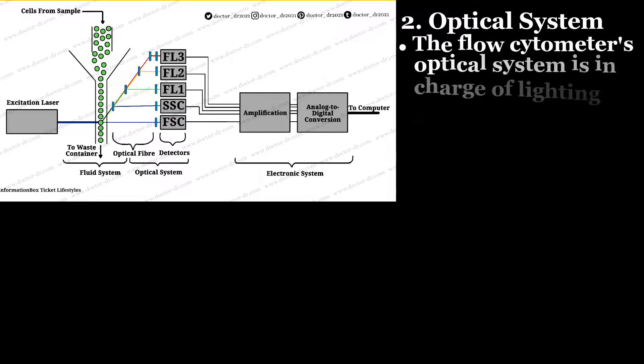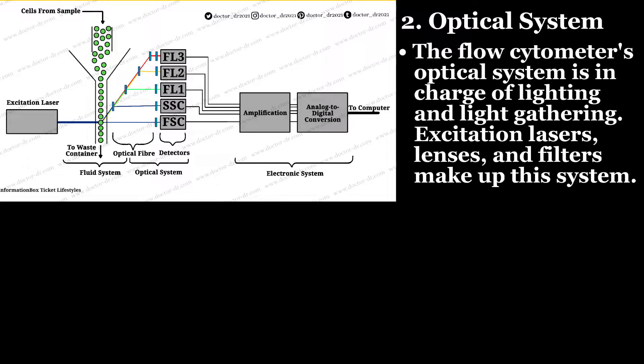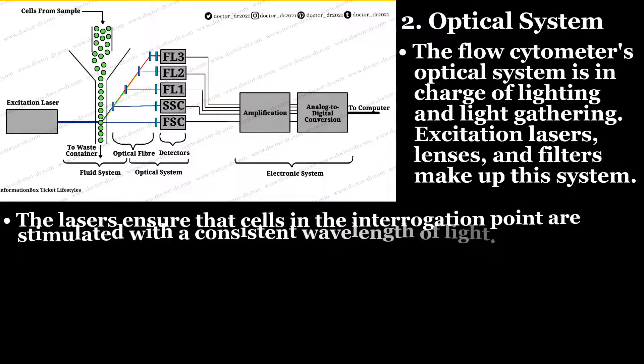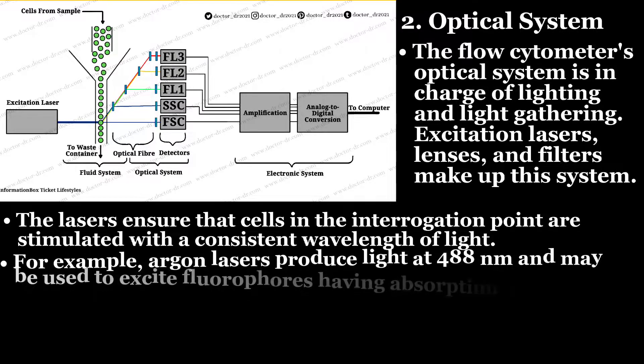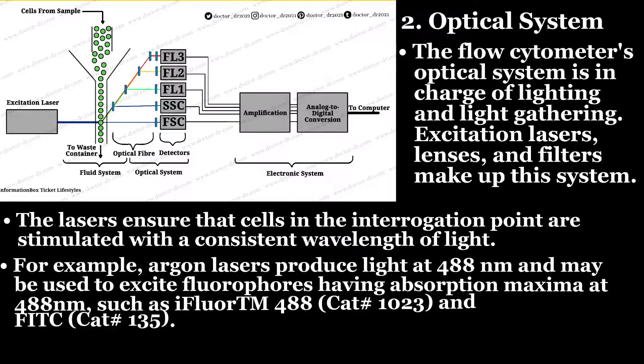Number two, the optical system. The flow cytometer's optical system is in charge of lighting and light gathering. Excitation lasers and filters make up this system. The lasers ensure that cells in the interrogation point are stimulated with a consistent wavelength of light. For example, argon lasers produce light at 488 nanometers and may be used to excite fluorophores having absorption maxima at 488 nm, such as iFluor™ 488 (cat number 1023) and FITC (cat number 135).